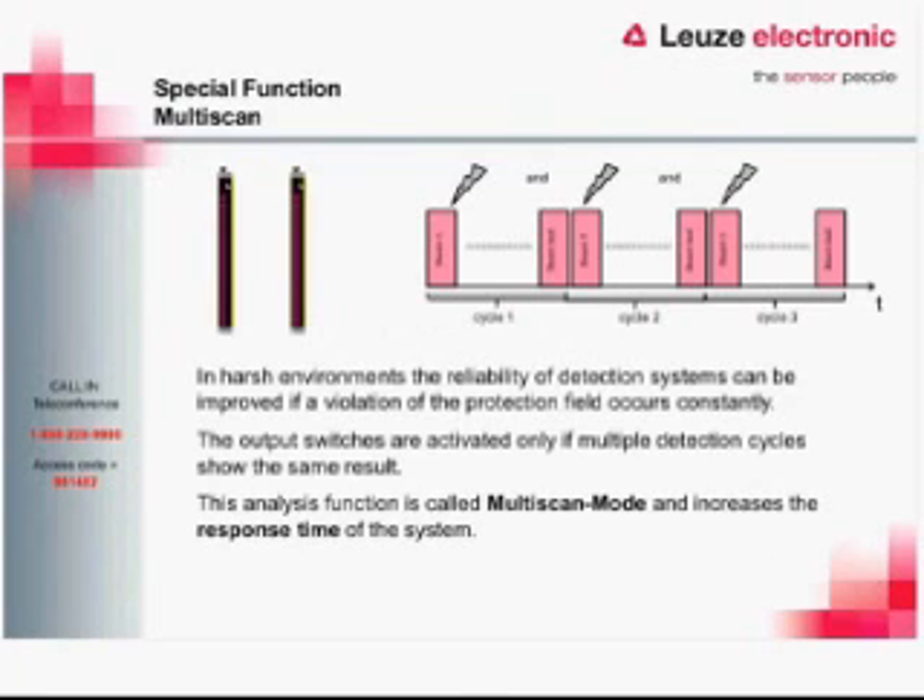The first extended function is multi-scan. Basically, if you were to break a light curtain with your hand, a forklift, or anything passing through the light barrier, on the first scan it will detect that and turn off the OSSD outputs. In a harsher environment where chips are flying or a weld slag passes through the field, we don't want it to trip every time something small passes at high speed. So we can enable multi-scan, which ensures it sees something in that field for more than one scan.